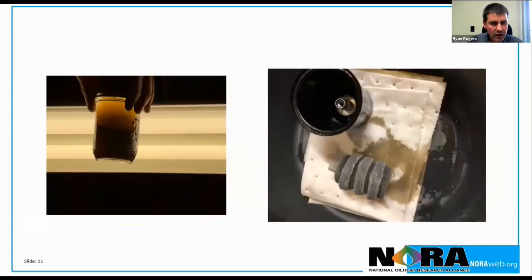And as you can see, as the weeks went on, the fuel kept getting clearer and clearer. The filters became cleaner and cleaner. And one thing I was very amazed at is how clean this fuel burns. I noticed really not a lot of buildup. In my boiler, it brought my stack temperature down almost 200 degrees because of the air reduction. And a lot of the issues that we were anticipating did not occur. The fuel burned extremely well.